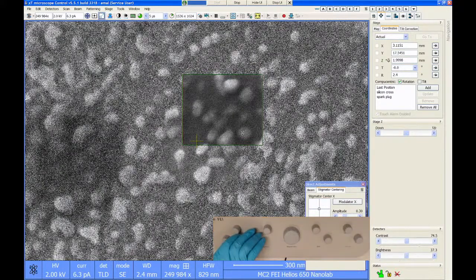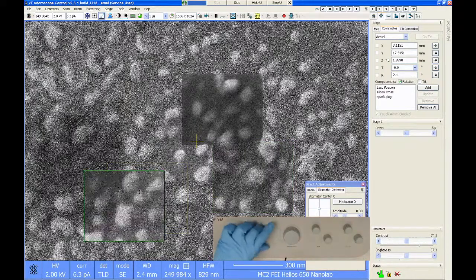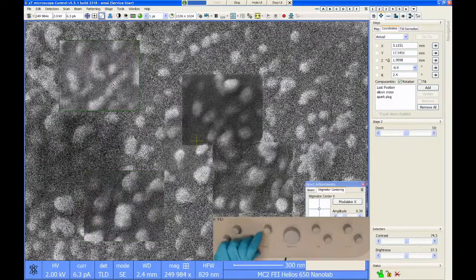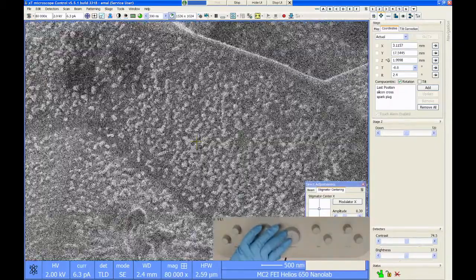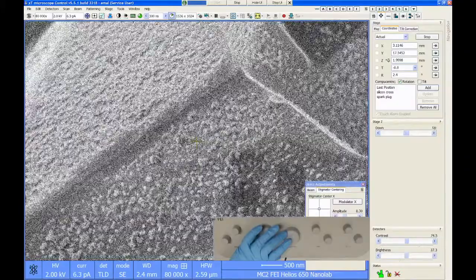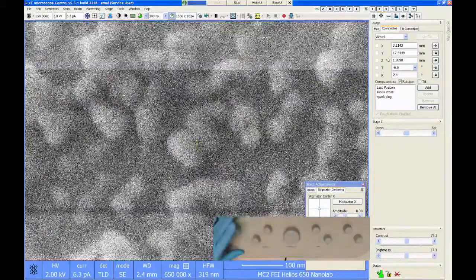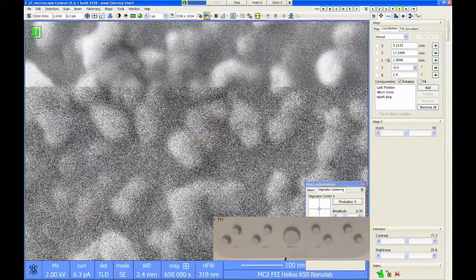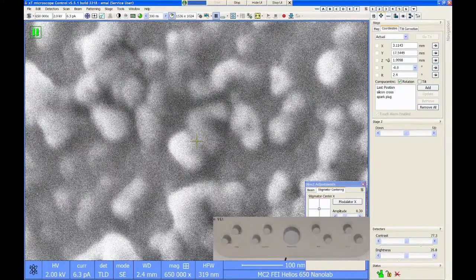Now, one thing that's a little tricky is that I don't know if this sample has features that are like a couple nanometers. So I'm not really sure if we're actually going to see anything smaller than that like 7 nanometer particle. All right, so let me get to a cleaner spot here. All right, so we were at, I think, 650,000x.